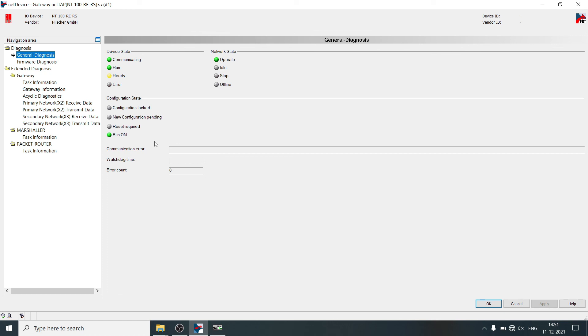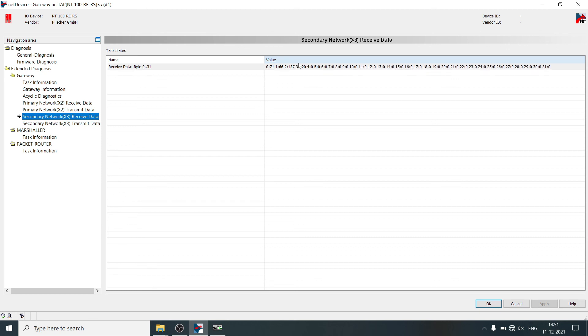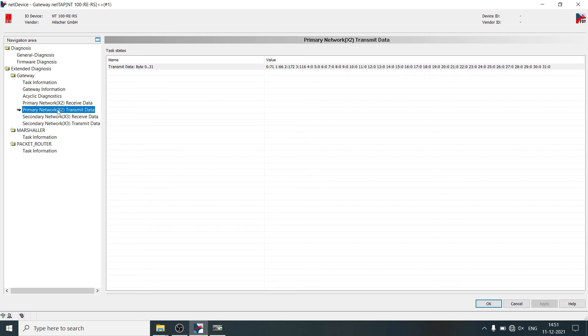Proper communication and mapping can be checked from receive and transmit data. This shows data from Modbus RTU energy meter, and this same data transmitting to the Modbus TCP client application.